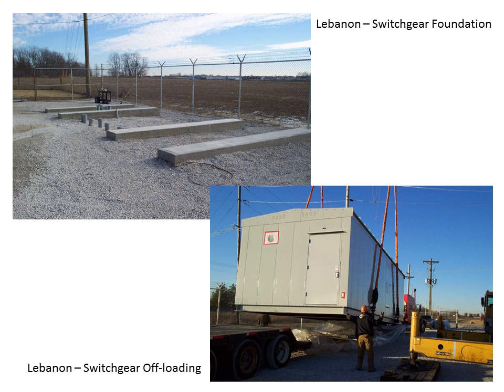If you'll look at that metal enclosed cabinet and look back at what we showed you in Greenfield with the Hastings Park sub and the open air sub, the same equipment in this metal enclosed cabinet performs the same function as the switchgear at the Hastings Park sub. We use this type of installation when our footprint for the station is much smaller, and we maybe only have a half an acre or an acre of property, not 2 acres.